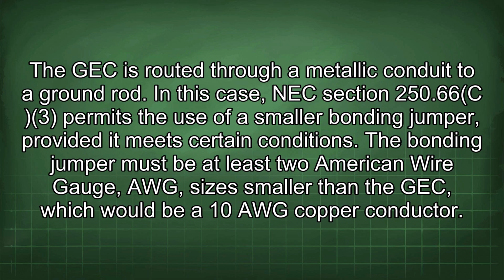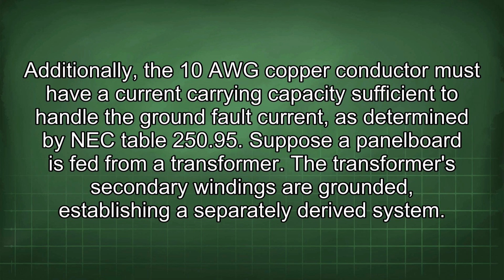In this case, NEC section 250.66(C)(3) permits the use of a smaller bonding jumper, provided it meets certain conditions. The bonding jumper must be at least 2 American wire gauge, AWG, sizes smaller than the GEC, which would be a 10 AWG copper conductor. Additionally, the 10 AWG copper conductor must have a current carrying capacity sufficient to handle the ground fault current, as determined by NEC Table 250.95.